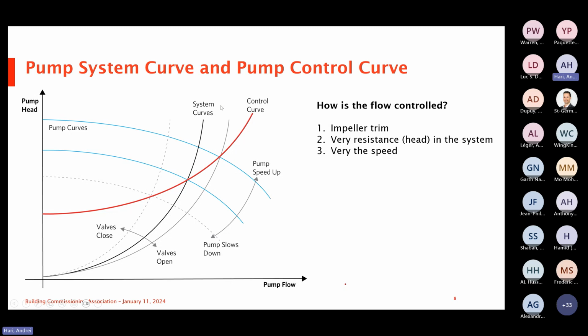So a lot of times what I find in the industry is that engineers will confuse the control curve with the system curve. And just remember, the system curve is a function of the system as water is moving through the piping network. And as you know, it's exponential, right? Flow increases, the resistance increases by the square. So where the system curve crosses the control curve at a certain speed is where that pump is operating. And everybody, I will provide this slide deck to anybody who wants it after this presentation.